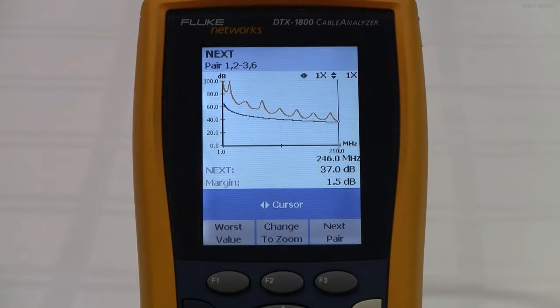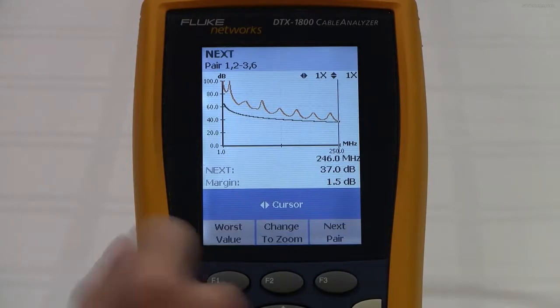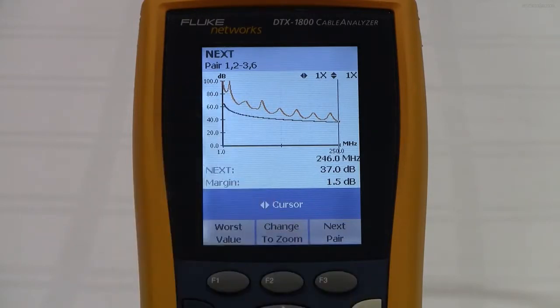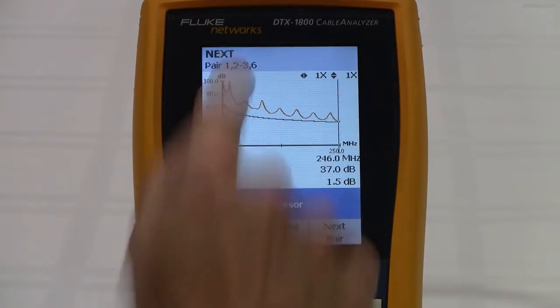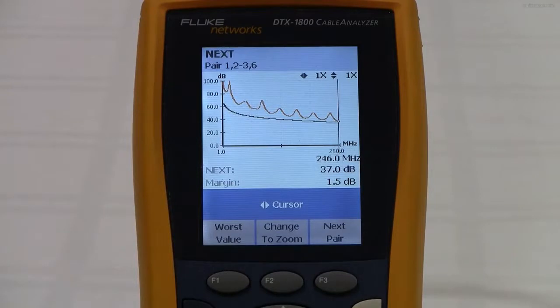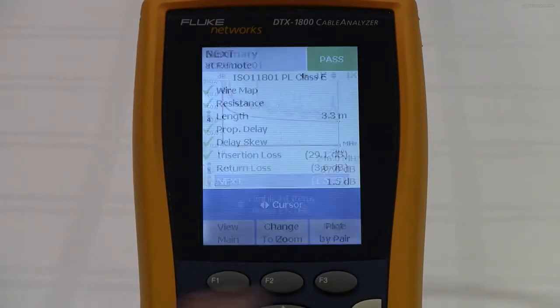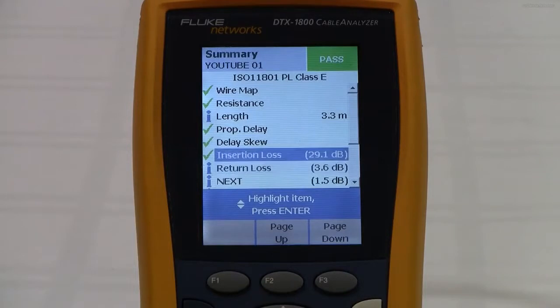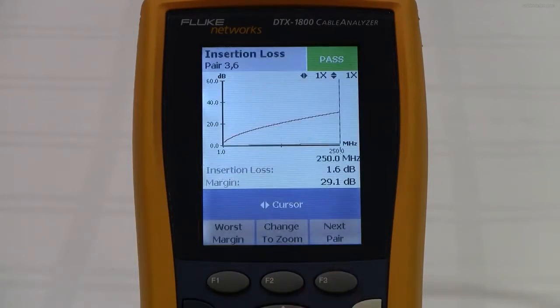look at it, and if it's less than 4 dB, then we're going to ignore that near-end crosstalk measurement. And when that happens, at every frequency point that evaluation happens at, we turn the limit line from red to black. Given that the entire limit line is black, that suggests the insertion loss for pair 3.6 never actually reached 4 dB. Let's take a look. And indeed, at 250 MHz, our insertion loss was only 1.6 dB, hence the entire measurement was ignored.